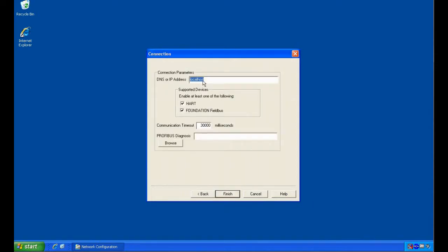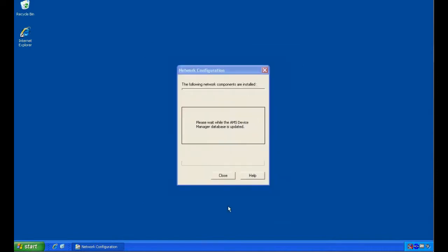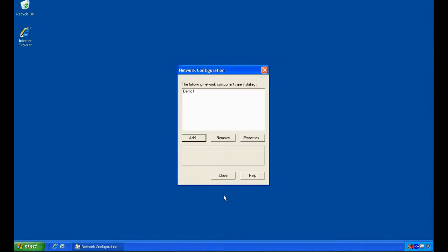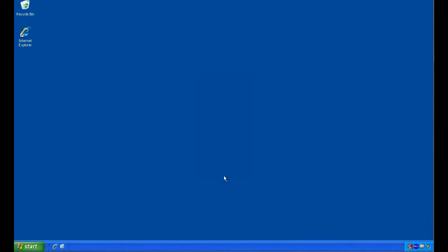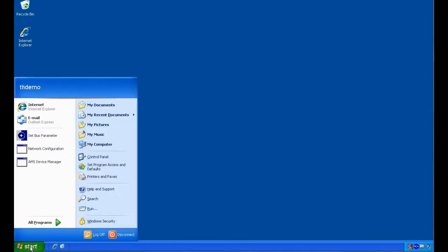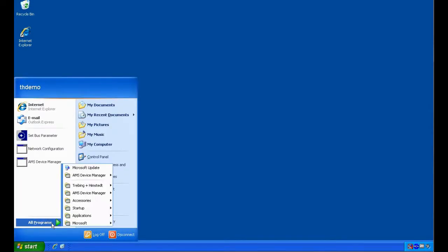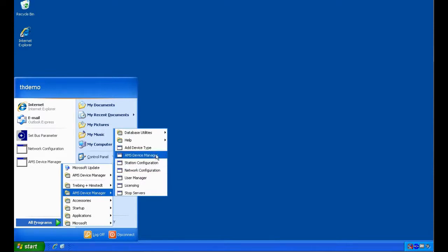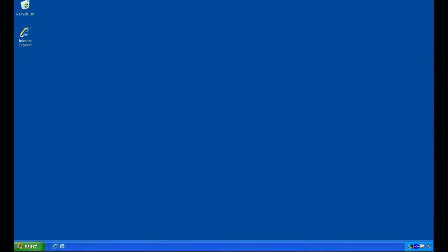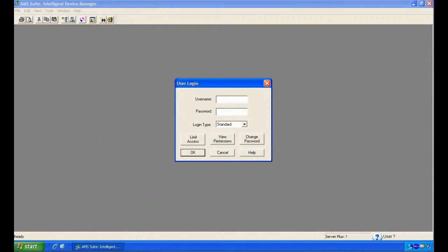And that's it. Then we have the connection parameters, and here it's important to keep the parameters, especially the localhost setting. By clicking the finish button, it's done, and we have our Profibus network as demo 1 configured on the AMS side. Now we have completed all our configuration, and we are ready to use HART Over Profibus with our AMS Device Manager.